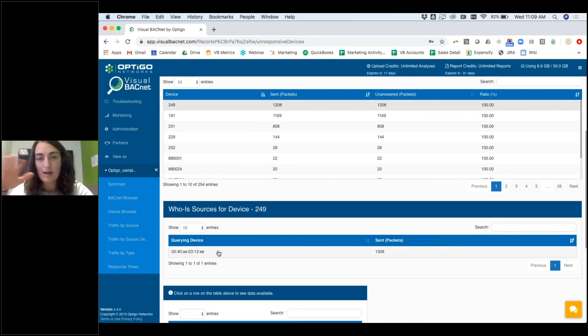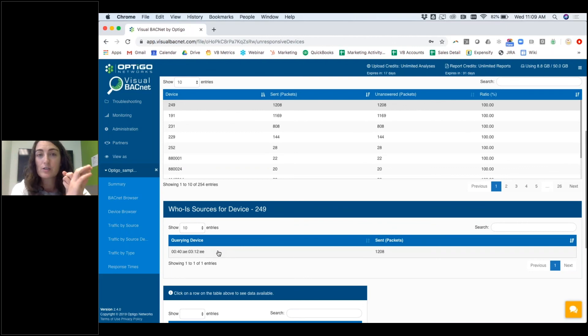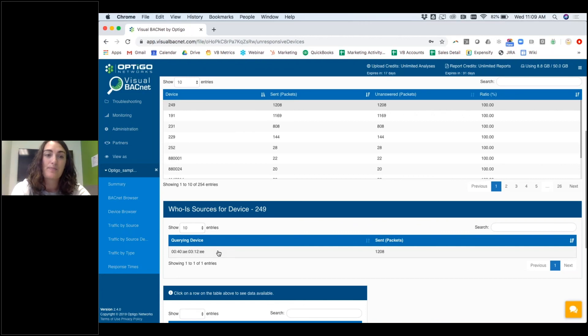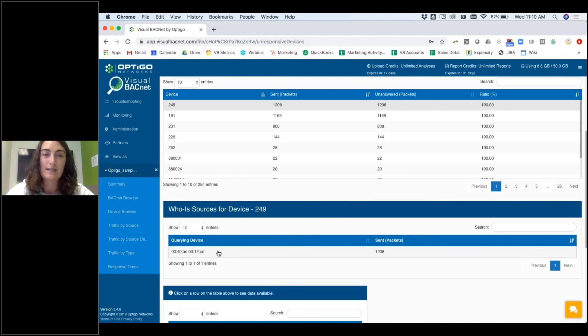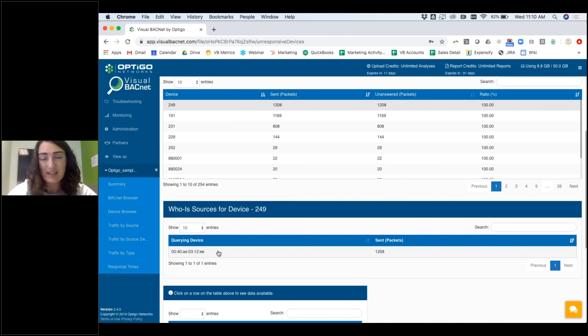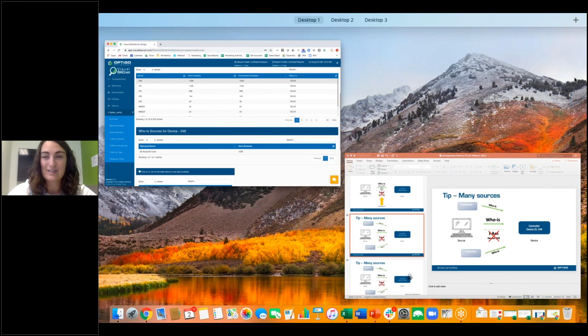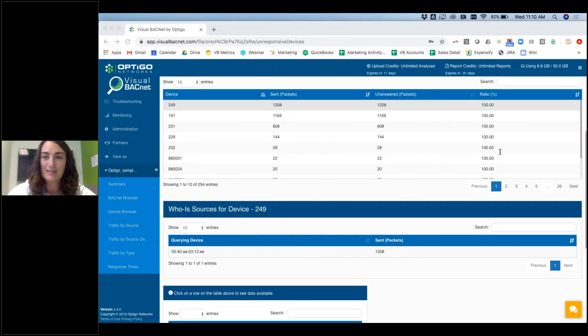On the flip side, if you have only one querying device — like with device 249 — it's more likely that someone forgot to change a default, or that device was pulled from somewhere else on the network and never updated. I often use the number of querying devices as a way to get an idea of whether the destination device is failing or the source shouldn't be looking for it. It's not 100% accurate, but with no other context it's a good place to start. That's all for today — feel free to put any questions in the chat, and thank you so much for joining me!